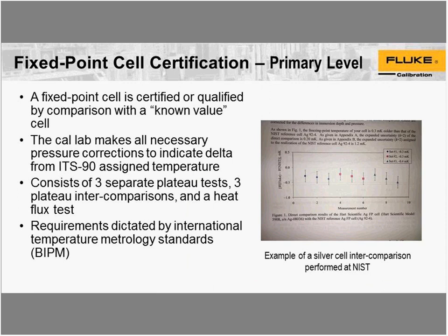It probably seems redundant, maybe, but I just want to reiterate that another key tool for verifying or controlling fixed point error is getting the cell certified. Especially with cells, we don't know what the pressure is inside. We're sure what it is because we manufacture them, we test them, and we see that the process works very consistently. But I talked about how things can change. The only way to know for sure is to get the cell certified.